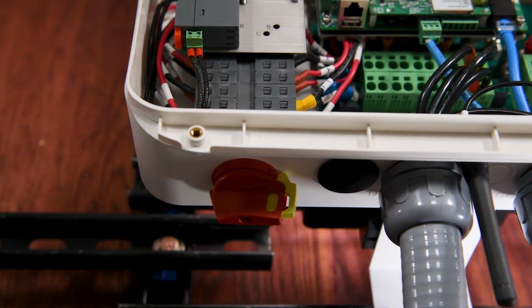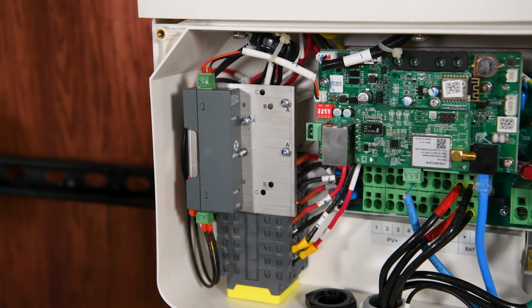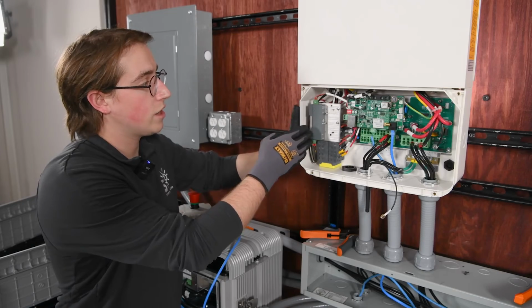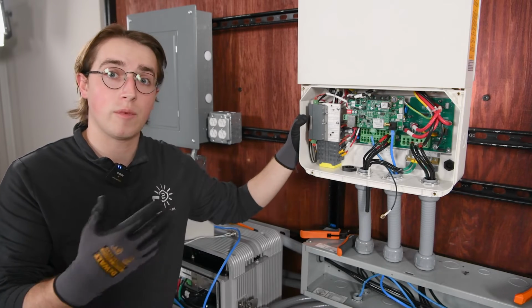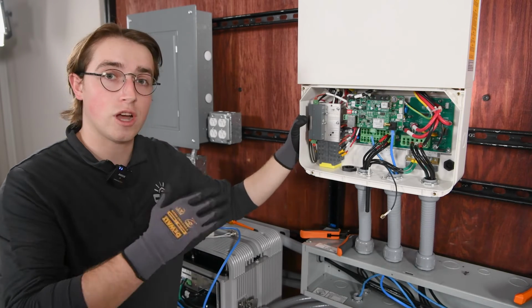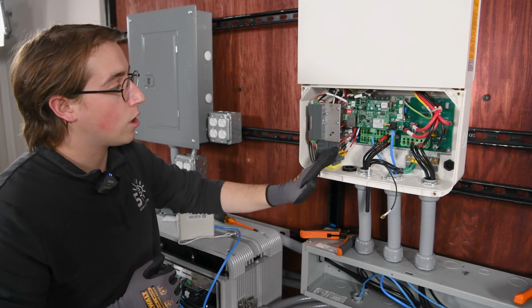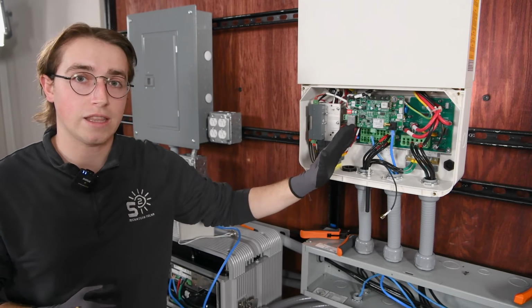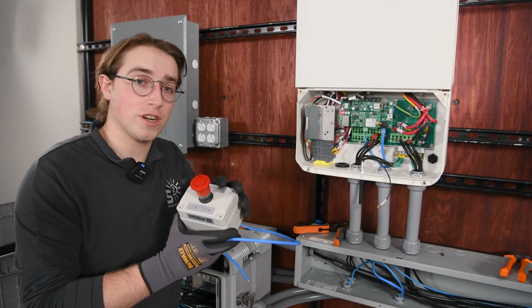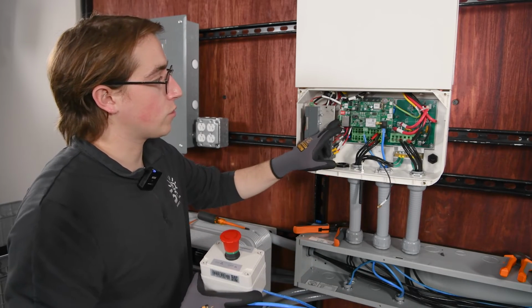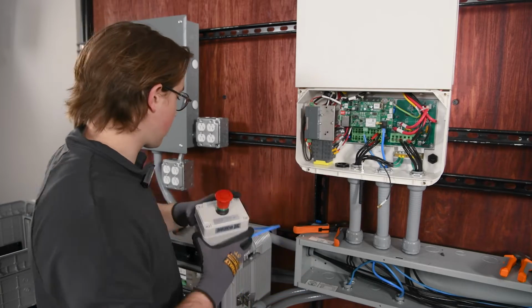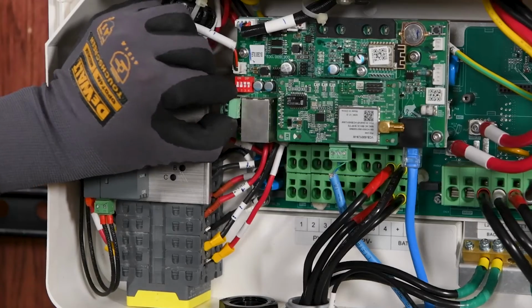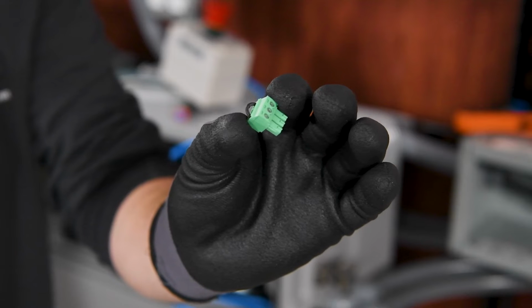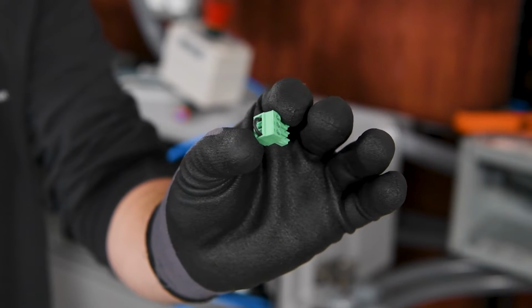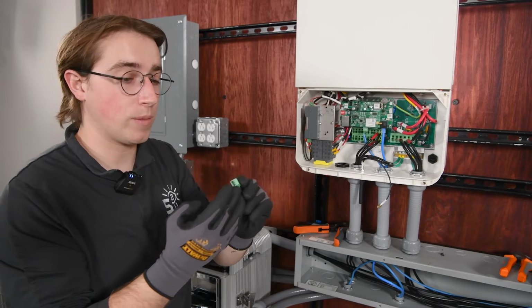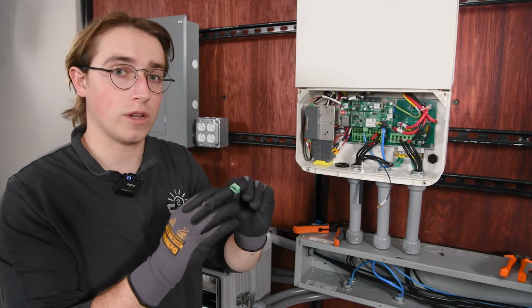Once the switch is initiated, our AP Smart or our Tigo transmitter will send the signal to our optimizers or our MLPEs on the roof and essentially stop power from the array coming down the line, but it will also disconnect the PV power directly at the inverter. To set up an external rapid shutdown transmitter, we are going to remove this 3-pin connection right here on the side of the comms board. And this already has a little wire that connects our far left and our far right terminals. Again, this is signaling to me and to us that this is going to be a normally closed circuit.